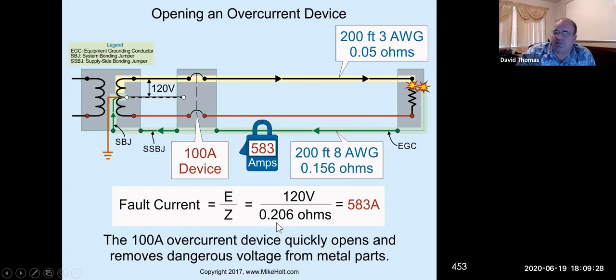0.156 comes up with 0.206 ohms, which means that if we know the impedance or the resistance of the circuit, we can calculate the amount of current that we're going to have during a ground fault scenario. So in this case, we calculated that we should have 583 amps. 583 amps will trip this 100 amp breaker.